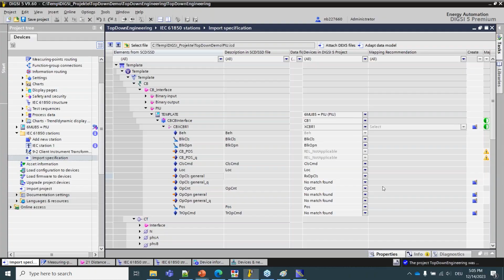You see that the majority of the required data objects are already provided in the device. Some are not there yet. This is especially the case for signals that will be received via GOOSE from the protection device. For that, we have the possibility to create external signals coming via GOOSE by creating them with that blue icon. The signal is now created and the match is found. I iterate the same for the other signal, and at the end, we end up with the required GOOSE inputs for the device.